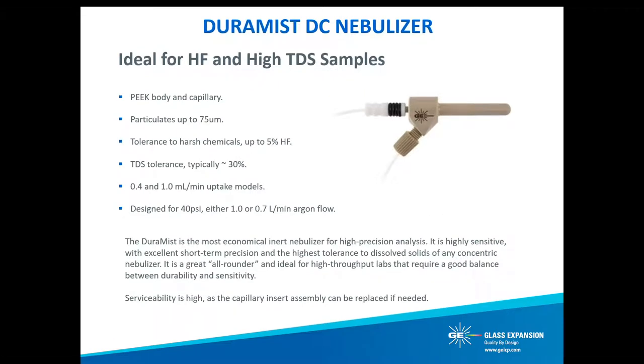The next nebulizer is our DuraMist concentric nebulizer — the first of our inert nebulizers. The DuraMist is made from PEEK and is our most economical inert nebulizer for high precision analysis. It's highly sensitive with excellent short-term precision and has the highest tolerance to dissolved solids of any concentric nebulizer. It's also a great all-rounder, ideal for high-throughput labs requiring a good balance between durability and sensitivity, especially for labs not interested in using a glass or quartz nebulizer. A unique feature is that the capillary insert assembly can be replaced at about a third of the cost of a new nebulizer if you experience a blockage that cannot be cleaned.